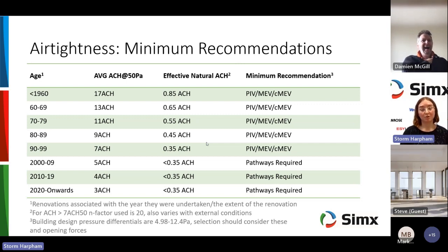Obviously, a lot of these homes still have moisture and condensation issues, but what we're saying is they're actually receiving the fresh air they require up until the late 90s. From 2000s onwards, though, not getting the natural air changes, and they're also becoming a lot more airtight. So what we're recommending here, and our recommendations are on the right, is that you look at any type of ventilation system, be it PIV, MEV, continuous mechanical extract, or even a heat recovery solution. So these are minimum recommendations. Anything before the 2000s is probably okay if they haven't renovated. On the other hand, after you've come through the 2000s, you need to start thinking about those recognized pathways for your air.